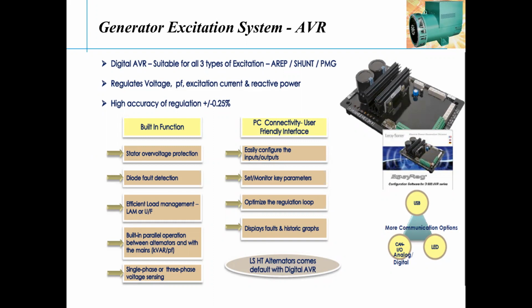This is customer-friendly, and you can just see on your own laptop what is happening in the excitation system or voltage. You connect a laptop, you can get everything. So it's the monitoring parameters. Always we keep monitoring the system, so that is available. Optimize the regulation loop, which is very, very important when it goes for regulation where the customer demand is like data centers coming across or critical equipment like commercial buildings. A small light flickering will irritate some people, correct? When power fails, a light flickering happens, we don't allow that. So this is a technology which has been brought across to meet those requirements.